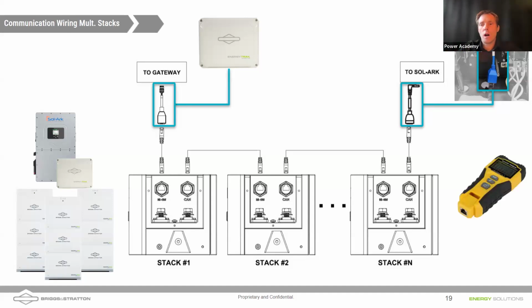So good question, Daniel, this is one of our favorite topics when we have installers out there. Actually, this just happened yesterday. I had somebody call in yesterday. We got that exclamation point on that Sol-Ark screen underneath the battery. And what that means is communications with the battery is not working properly. I had them swap cables. It was a bad cable, right? So there's a cable tester there on the screen. It's essentially a $30 item. Make sure to take those with you when you're wiring your comms up.